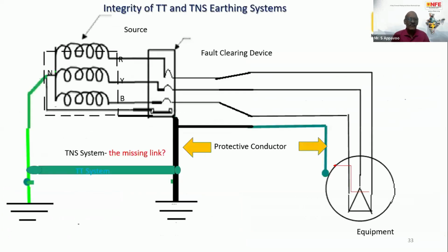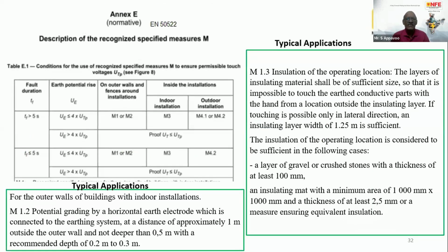So this is provided. For example, there are measures. It's a typical measure I have here. It is very simple. If you have an outer earth of a building, you can provide just a horizontal earth strip around the building. This is sufficient. This will help you to minimize the potential grading. It's a potential rise, that potential rise during lightning activity also. So you just go through these measures. So I'm giving only two measures as a sample.